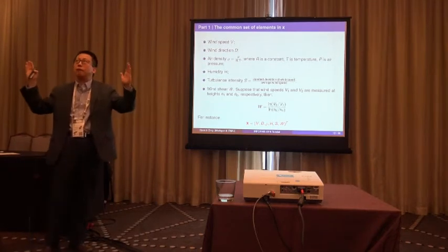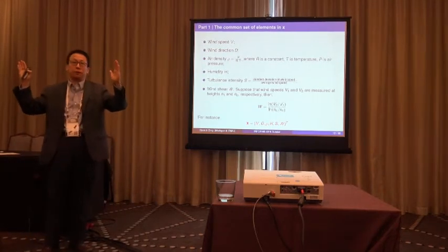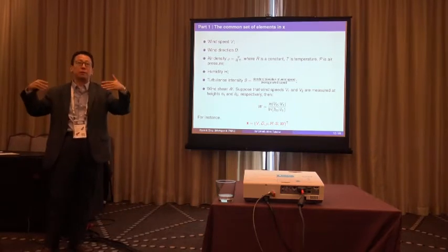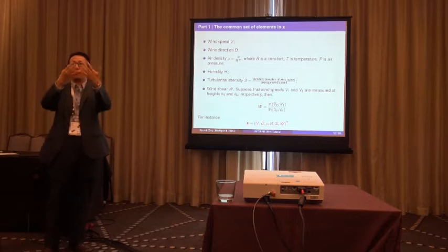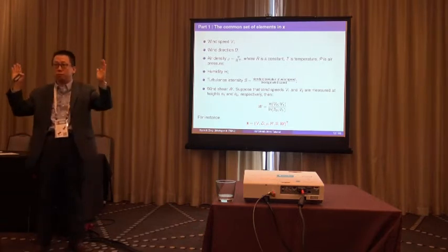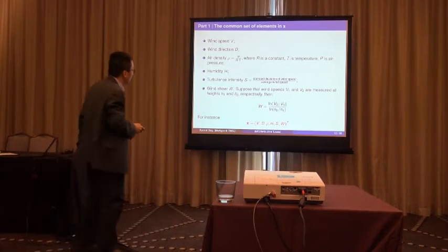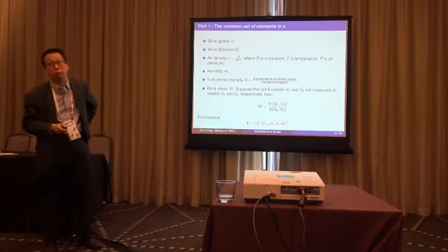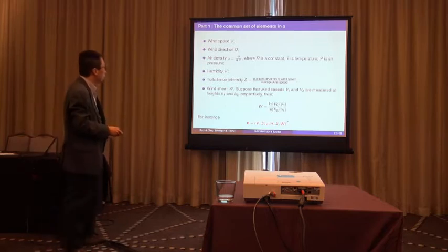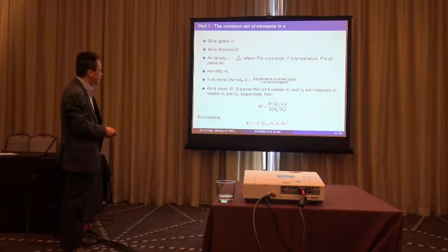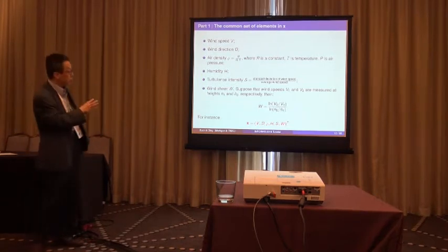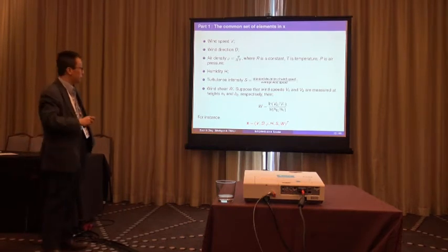Right now, I think it's not very easy to measure the horizontal wind shear, which sometimes is still needed. Okay, you need some kind of new sensor like a LiDAR in front of the wind turbine to measure the whole spectrum of the wind field to calculate the horizontal wind shear. Most of the time, for commercial wind farms, this kind of measurement is not commonly available. Okay? So, generally speaking, there are 6 variables, and depending on the availability of sensors, this can be expanded or shortened to some extent.